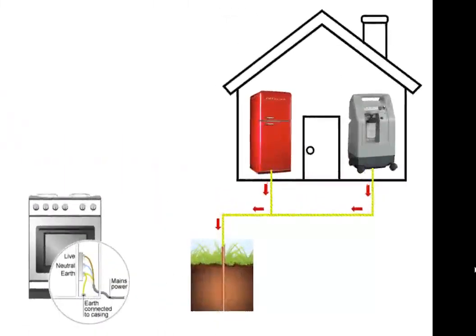The earthing system, in combination with protective devices such as circuit breakers and residual current circuit breakers, ensures the safety of the user of an electrical installation. A grounding system, also known as earthing system, creates a safe route for the current to flow into the ground if the phase or neutral wire touches the casing of electrical equipment.